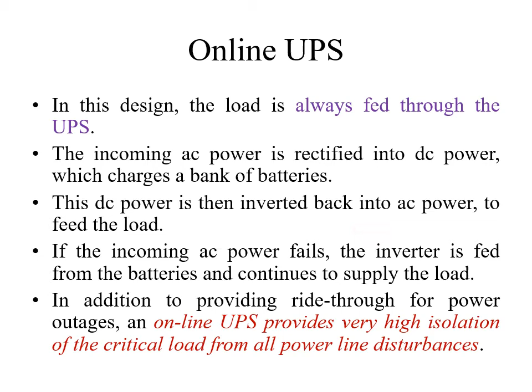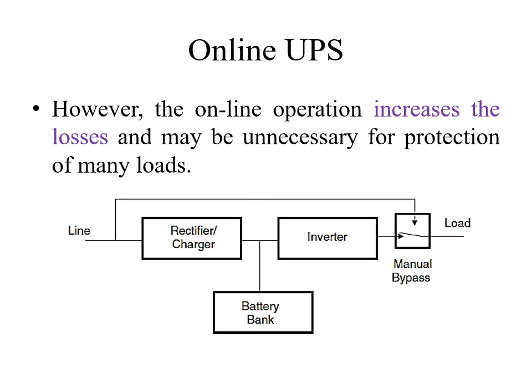When it comes to online UPS, this UPS is always connected to the load. That means the incoming power is rectified and converted to DC and stored in the battery, and then this stored DC power is converted back to AC power to feed the load. So if the power fails, the inverter is fed from the batteries and continues to supply the load. In this system, the battery is always connected. And here there is only one drawback: it increases the losses, because the rectifier, inverter, and battery are always connected to the system.